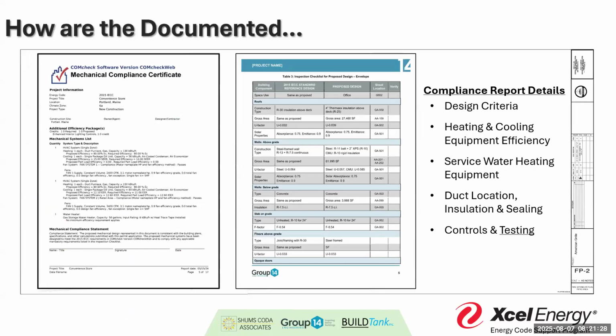A lot of that information can come out of the documentation we get provided. If I see a COMcheck that incorporates mechanical components, I understand it's not perfect, but it gives me a sense of what I'm expecting to see. If they've identified 3 systems - a water heater and 2 rooftop units - and then the actual plans show 7 different pieces of equipment, I'm going to have questions about the consistency throughout the entire project. If I see we're doing an energy report where they're utilizing specific energy efficiencies to justify other trade-offs, I need to know that so I can verify it in the totality of what I'm doing.